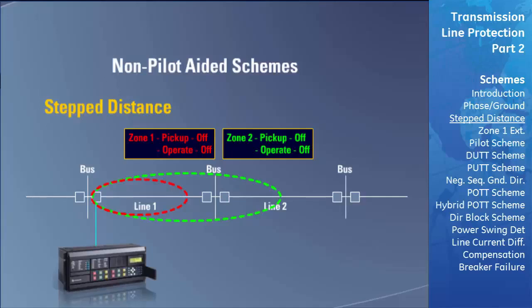If a fault occurs in the end zone region of the transmission line, the two zones act differently. The fault does not lie within zone 1's zone of protection, so zone 1 will not pick up. The fault does lie within zone 2's zone of protection, so zone 2 will pick up. After the zone 2 time delay expires, the zone 2 operate flag changes to the on state and triggers the relay to trip and clear the fault. Once cleared, both the pickup and operate flags of zone 2 turn off.